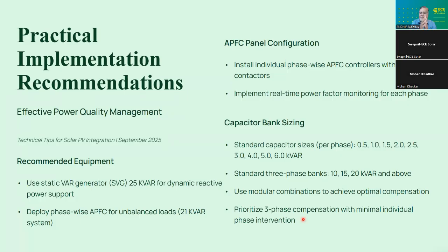We are talking of 40 kVA, kW connected load. We are talking of 30 kW, 25 kW connected load, and we need to have all the three phases balanced now. So the capacitor bank size will reduce to 0.25, 0.5, 1, 1.25 to 2.5. This kind of small steps will be required to have a fine tuning to 0.999 kind of a result.